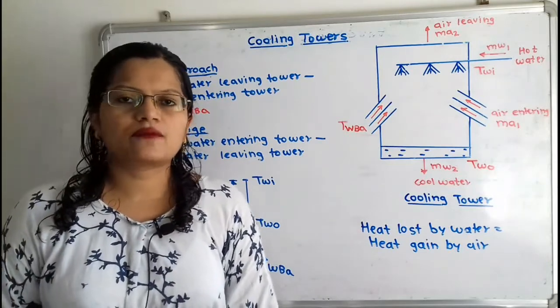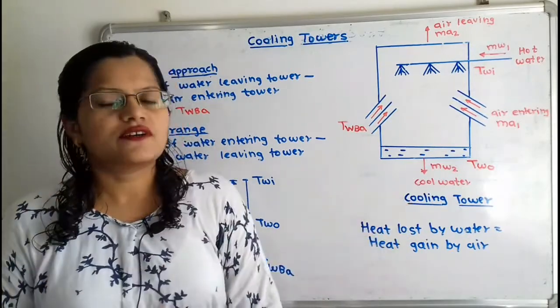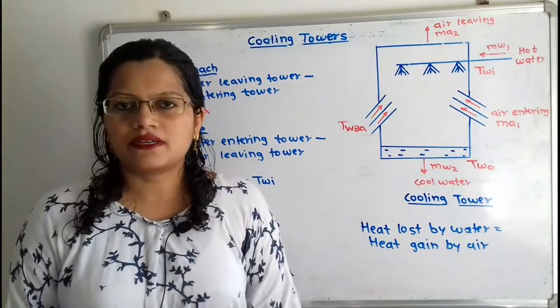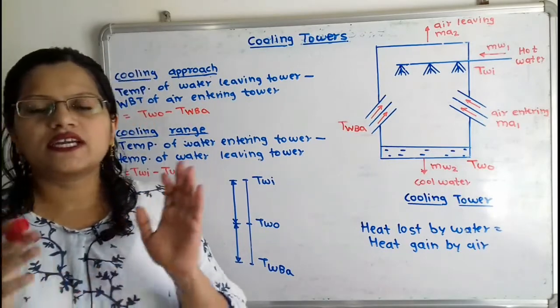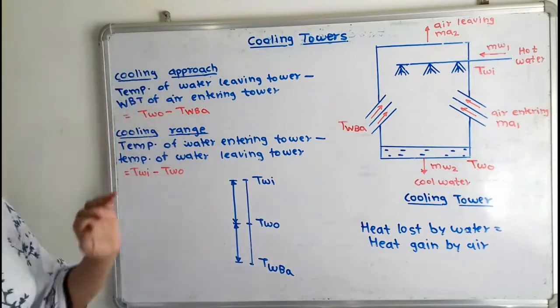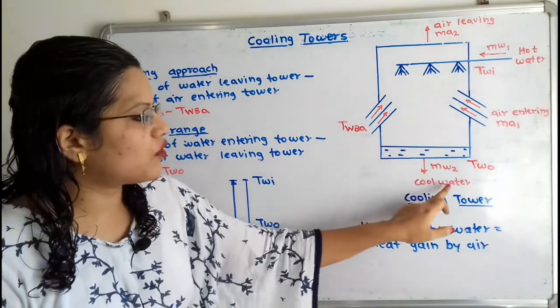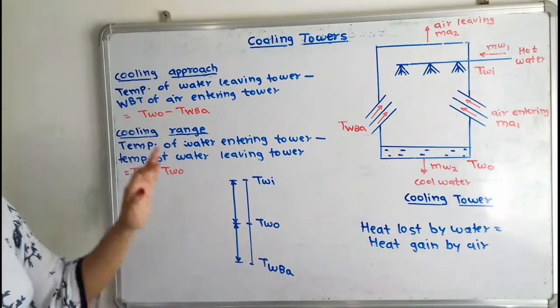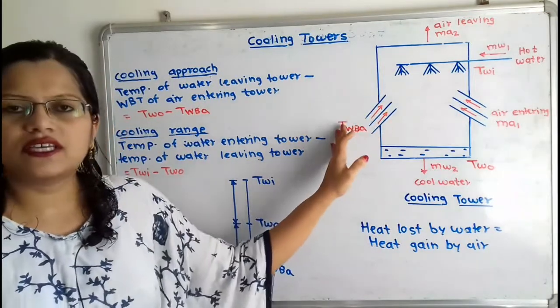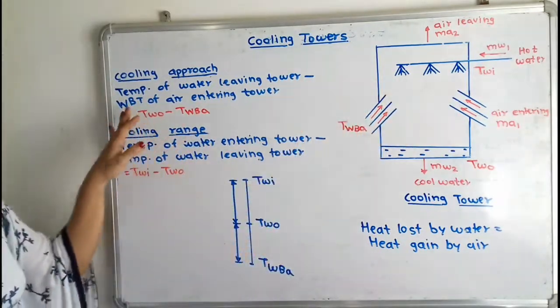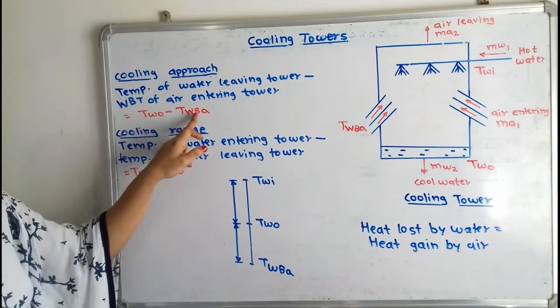These are the performance parameters for the cooling tower. The performance of a cooling tower is measured with the help of these two parameters. The first one is the cooling approach — it is the difference in temperature between the water leaving the tower (TWO) and the wet bulb temperature of air entering the tower. So cooling approach equals TWO minus TWB-A.